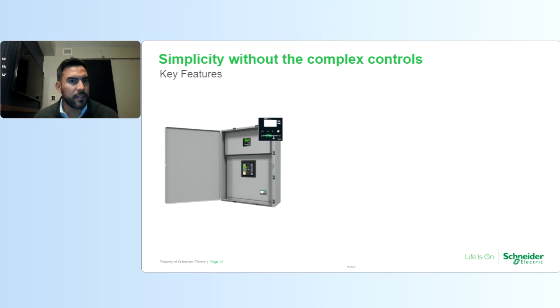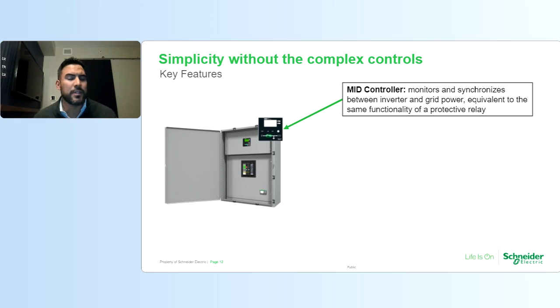So what makes SourcePack unique? I would say it's the simplicity without the complex controls. If we zoom into this microgrid interconnection device controller, it monitors and synchronizes between inverter and grid power, equivalent to the functionality of a protective relay. In today's industry, you'll very commonly see a Schweitzer relay being utilized, programmed and interconnected with some type of contactor, and that protective relay senses an under voltage setting. It would open that contactor, and then when utility returns, it will close that contactor again. That solution works for most applications. However, that solution is not truly UL listed for the automatic interconnection functionality for emergency systems.